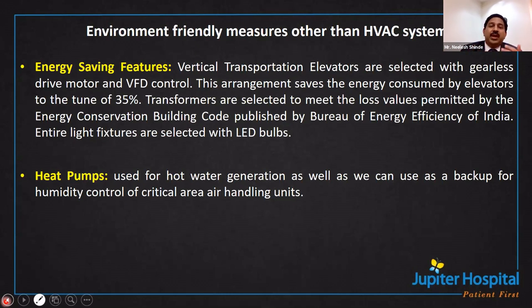So this is where the BMS comes into the picture. If you maintain 21 or 22 degrees throughout, 24 hours, no saving is going to happen. But if you set up the BMS in such a way that at night, whenever it is of no use, we can change the temperature, it will really give us great energy saving. Like what we have done: there is a medical equipment room where the UPS is kept. For UPS and battery, 25 degrees is also no issue at all. That is an acceptable thing.